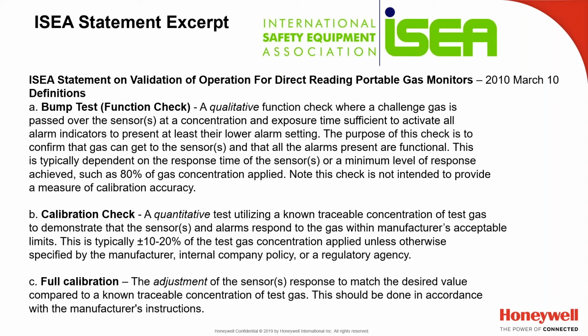That's a quantitative test where we can actually set up the docks for that threshold of 80 or 90%, not just the lower alarm, which is around the 40% range of the go, no go qualitative function check. The quantitative function check is just that. It's going to look at the value of the cylinder's gas levels for CO, 100 ppm. The BW mix is 100 ppm CO, 25 ppm H2S, 18% oxygen, and 50% LEL methane. And it's going to accept it in this particular case if it's plus or minus 10 or 20%. Understand the gas itself has a tolerance of plus or minus 5%, so you can't really ask a gas monitor to be any better than that.